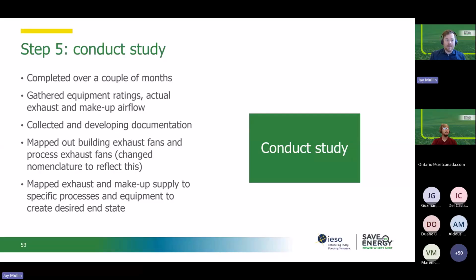So when they were going through this, mapping everything out and doing those design flows, they wanted to make sure that how things were labeled in documentation was really clear about what they were for. So they implemented a consistent, clear naming framework for all of the different exhaust and supply units, to make sure that a building exhaust fan was easily distinguishable from a process exhaust fan. So that really fed into that intent around informing the BAS. And that mapping was a really involved process. I think Craig said he spent a week on the roof mapping out all the different exhaust and makeup air units, air handling units, and rooftop units that were up there. So it was a process to do that.